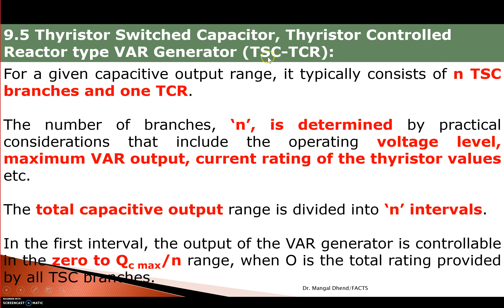This SVC is a combination of TSC and TCR, so it will give VAR controlling capability from absorbing power to supplying power. TCR will absorb power from the power system during light load periods when the power system is supplying reactive power. Somebody should be there to absorb that reactive power, so the reactor should be on to absorb it. When load is higher, TSC will inject reactive power and TCR will be absorbing power.